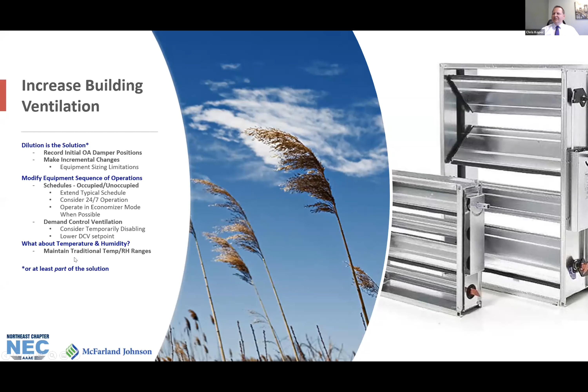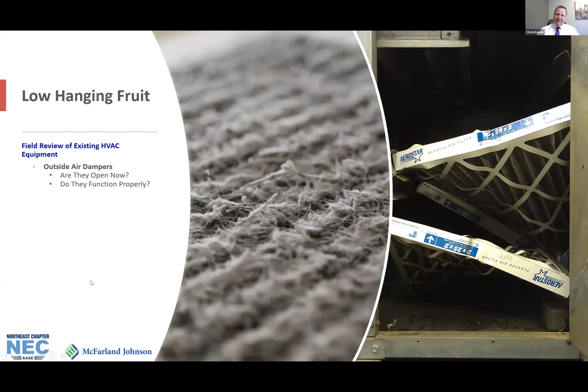So I strongly recommend conducting a field review of all your centralized HVAC equipment to make sure it's operating properly. If you've ever heard of commissioning or retro commissioning, this is essentially what it is. It's a systematic review of your HVAC equipment to ensure it's functioning as the design intended. Basically, your best investment is making sure the money you've already spent on this equipment isn't going to waste and your equipment is working to the best of its ability. It's relatively inexpensive. It can be performed by your maintenance staff or your preferred engineering consultant.